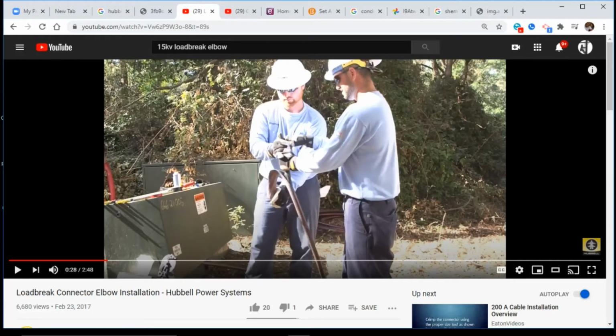Yeah. I mean, I'd be so generous as to say, if I know I'm going to be installing an elbow, my elbow connection is going to be in this area down here. I'm going to pull about 6 to 10 extra feet out of both ends. So if this is going down to another transformer down here on the left-hand side, I'm going to have 10 feet of wire primary hanging out. On this side, I'm going to have 10 feet out. Just to make sure that I've got enough ground conductor. One, I'm able to train the cable into the enclosure. And just by chance, if I make a mistake, I've got more to work with. I don't have to pull the whole span again.